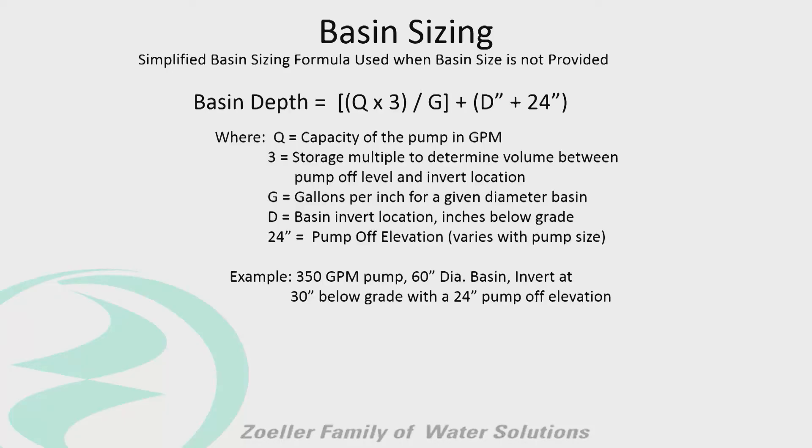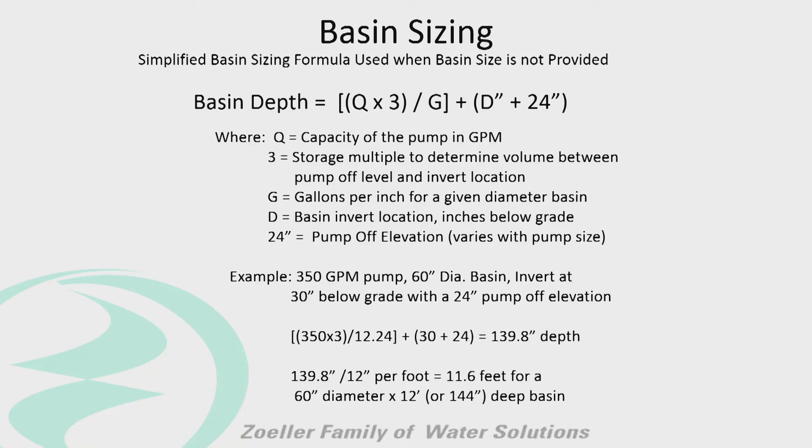Here's an example. The pump will do 350 gallons per minute, and they'd like to use a 60-inch diameter basin. The invert is at 30 inches below grade, and the pump shuts off at 24 inches. Plugging it in: 350 times 3, divided by 12.24 — which is the gallons per inch a 60-inch basin holds — then add 30 and 24. The result is they need a 12-foot deep basin, approximately 11.6 feet. So a 60-inch by 144-inch deep basin is what's required for this application.